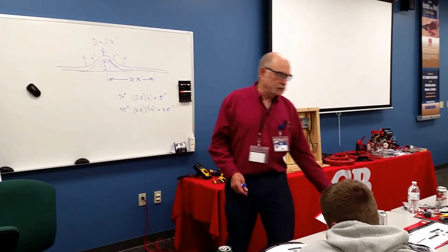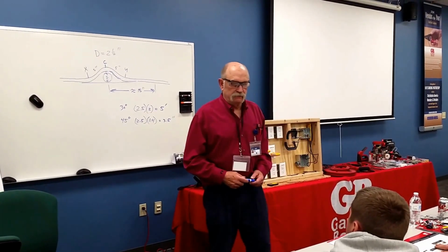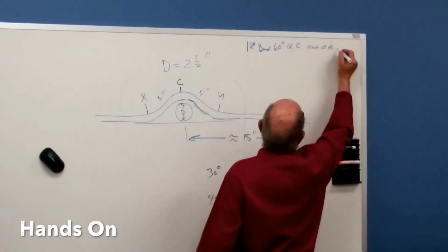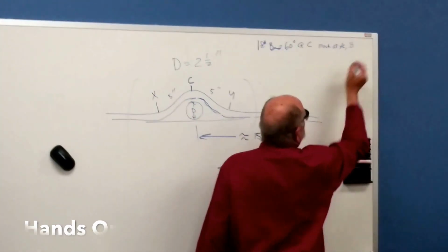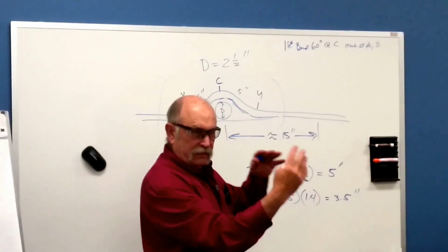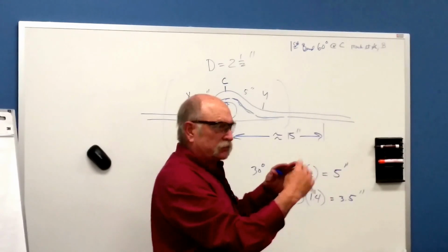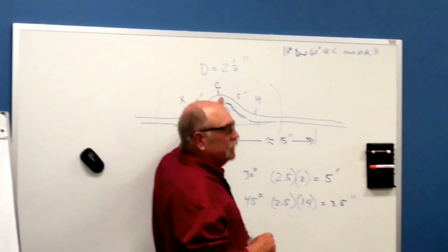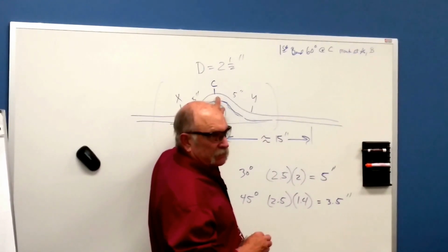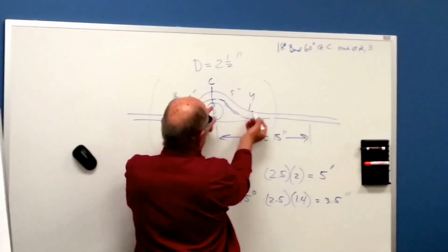Okay, good. So let's go do that. At the star or the B, depending on what you got on your bender. So that's inside, that's after the arrow. So the mark, either the star or the B, is actually going to be the center of that bend. Okay, that's the center here, because that's where C is, right? If you measure 5 inches that way, 5 inches that way.